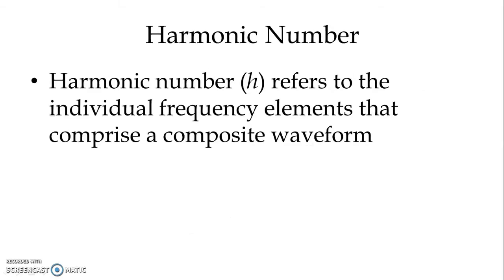We start with harmonic numbers. Harmonic number h refers to the individual frequency elements that comprise a composite waveform. For example, when we refer to a fifth harmonic, it refers to the frequency which is five times the fundamental frequency. For example, with fundamental frequency 50 Hz, the frequency for the fifth harmonic will be 250 Hz. Same way, the seventh harmonic refers to a frequency seven times the fundamental frequency, that is 350 Hz.